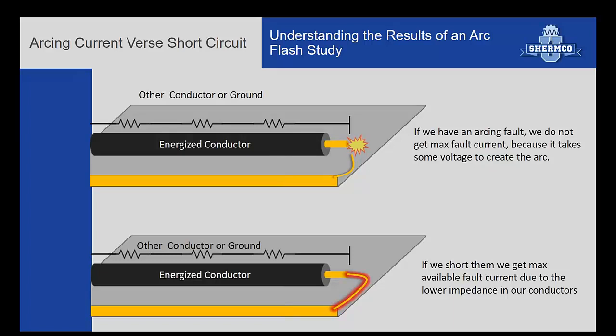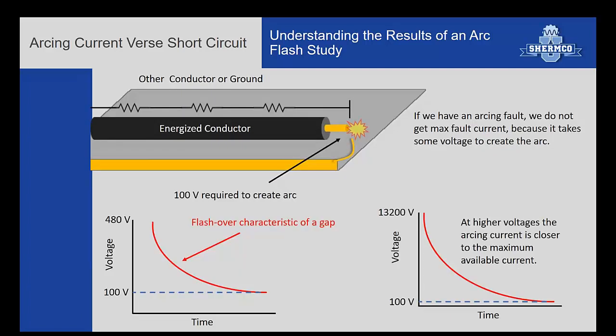and their impedance. Arcing current, it takes some amount of voltage to make an arc. So you're not dead shorted. You've got this gap, which takes some voltage. So you're going to have much less arcing current versus short circuit. We tried to give an example. For example, if it takes 100 volts to make an arc on a 480 volt system, you're really only left with 380 volts to pull whatever amount of arcing current would be pulled. And 100 volts compared to 480, that's about a quarter of your voltage.